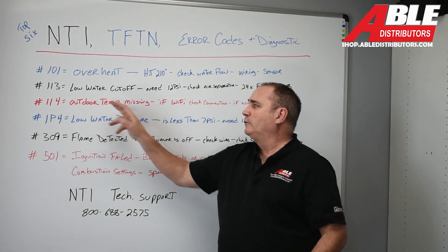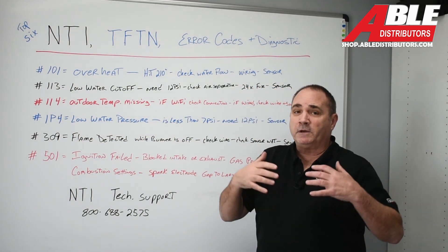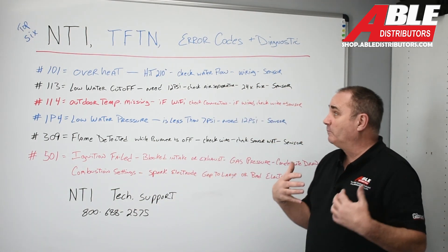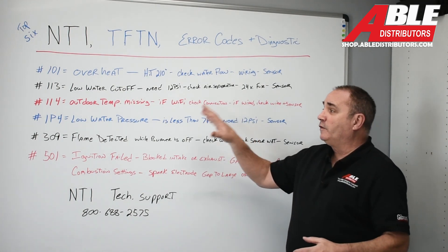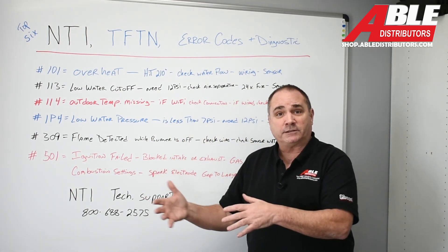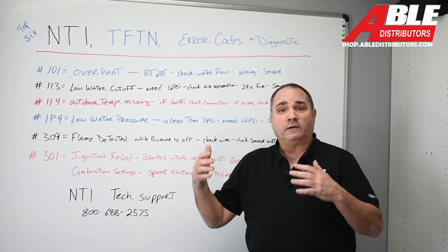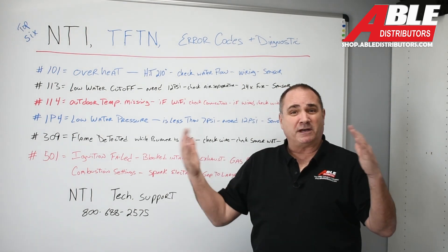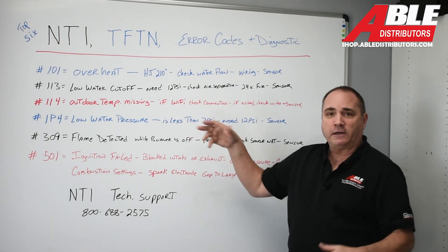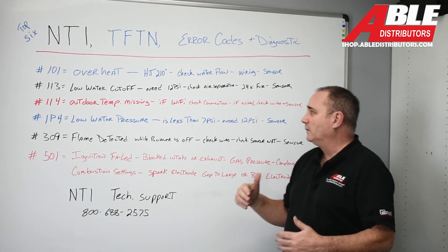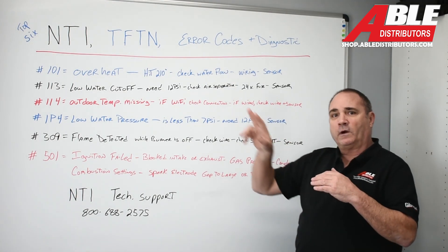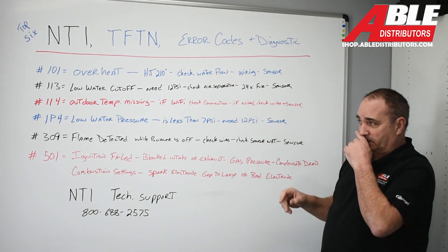Code 114: outdoor temperature missing. This means you had an outdoor temperature sensor wired there and for some reason the board's not picking it up. With this boiler you can do that via Wi-Fi to take advantage of outdoor resets — on a day like today in February when it's 50 degrees out, you might not have to fire that boiler all the way. If you connected it via Wi-Fi, make sure you didn't lose that signal. If you connected it wired, check the wire going outside and check that sensor outside.